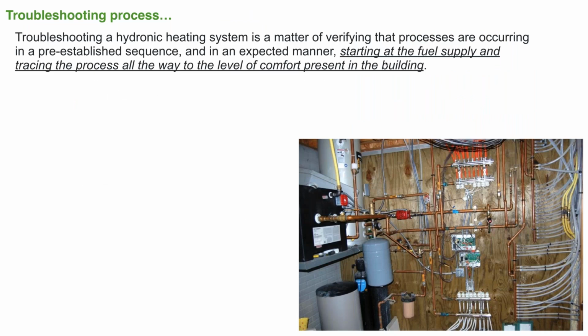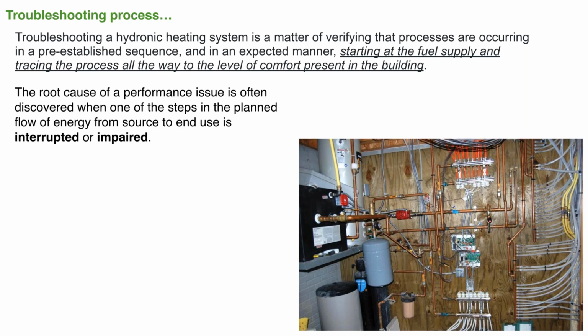Now let's talk about the troubleshooting process. Troubleshooting a hydronic system is a matter of verifying many processes that are supposed to occur in some pre-established sequence and in an expected manner. And I've put down here, start at the fuel supply and trace these various steps all the way through to the level of comfort present in the building. The root cause of a performance issue is often discovered when one of the steps in that overall process is lacking or isn't occurring as expected. It's being interrupted or impaired by something.